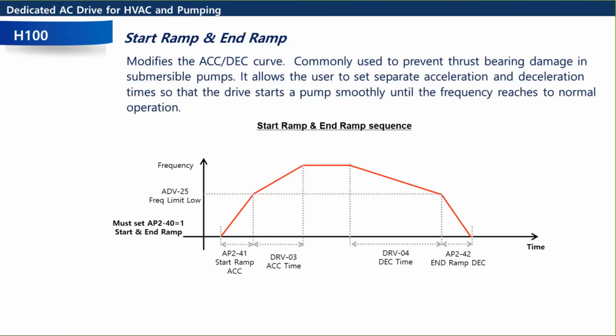So with start ramp and end ramp, you have a short acceleration time up to whatever your lower limit is. Let's use the example I just mentioned. Typically it's 30 hertz. So you set your lower limit to 30 hertz, and then you have a 1 second acceleration time to get up to 30 hertz. After that, you can have a longer acceleration time. Same thing on the decel. Maybe a long decel until you hit that minimum, then you want to ramp down fast, because you don't want to be riding on those thrust bearings when they're not properly lubricated and riding on the water that you're pumping.